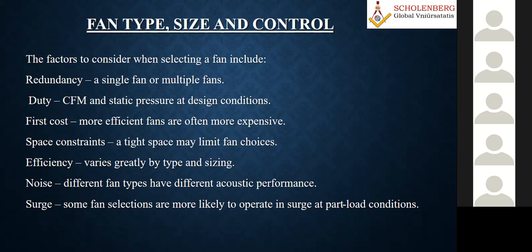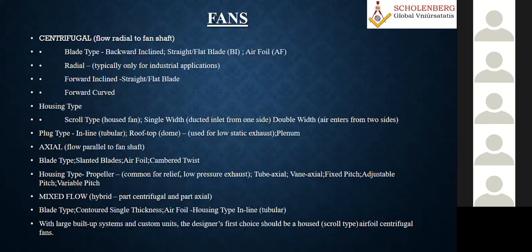And again, depending upon the fan efficiency, the fan efficiency curves are available. And then definitely when you go for any centrifugal machine, there is surge. You know, surging in the centrifugal, whether it is a pump or a blower, surging is another important issue, and the part load condition. So that is also to be addressed during your design stage. Talking mostly about air handling units, you have the centrifugal type because it can be backward or straight or normal blade. And then for the housing type, it will be a scroll type, just like we see in a centrifugal. As I told you, there is not much difference between a centrifugal blower and a pump.